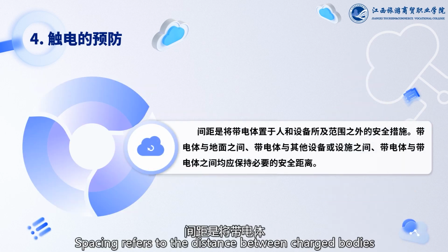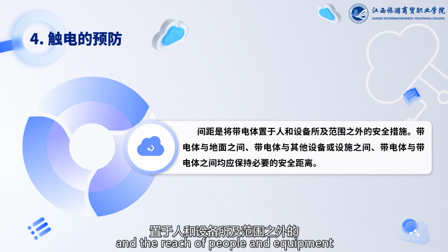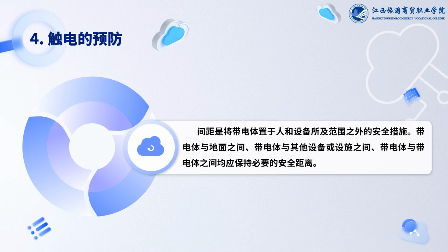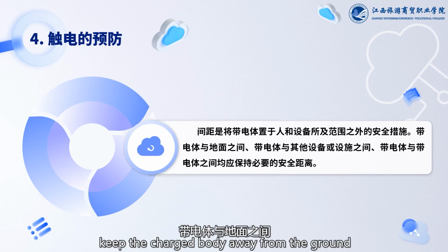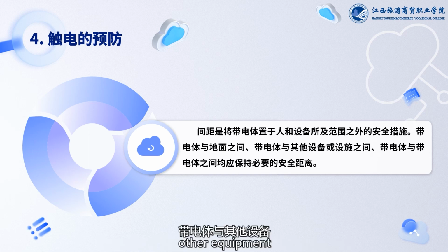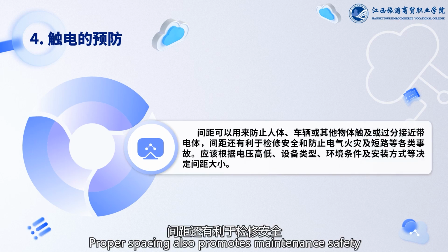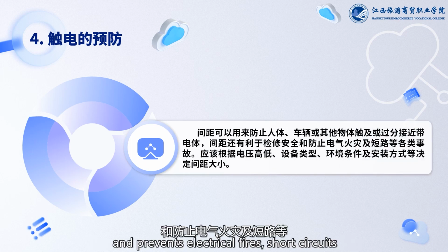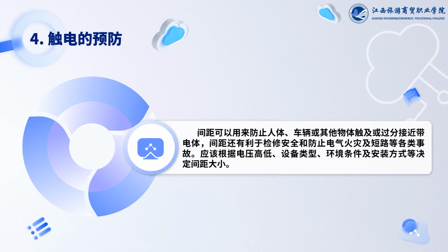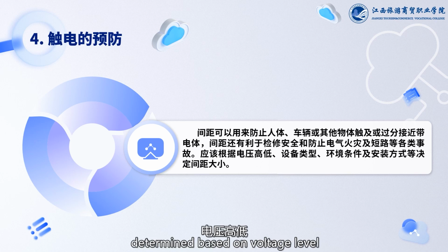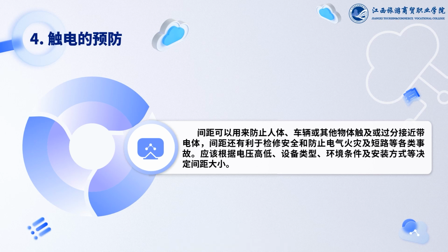Spacing refers to the distance between charged bodies and the reach of people and equipment. It is a safety measure to keep the charged body away from the ground, other equipment, and facilities with necessary safe distance maintained. Proper spacing also promotes maintenance safety and prevents electrical fires, short circuits, and other accidents. The spacing size should be determined based on voltage level, device type, environmental conditions and installation method, etc.